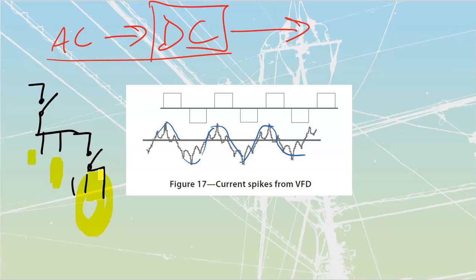It was inside of a multi-level commercial type of building. But they ended up having to trace it all the way back through the main panels, back up the sub-distribution, just by looking at the magnitude of the harmonic distortion that they were having inside of there. You do need to be there for a fairly long day. This is not a 5-minute stop in or anything like that.